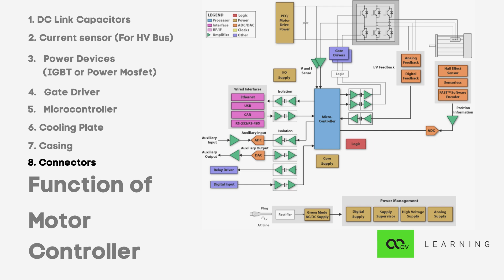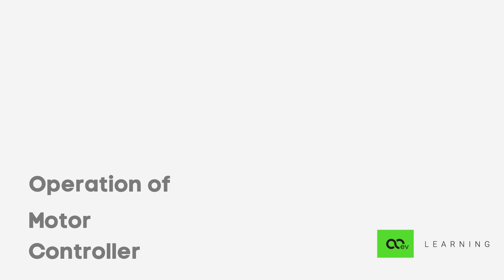Connection of higher voltages is solved by simple methods of lug-based connection with defined torques on the bolts to maintain the contact resistances in manageable levels. Specialized HV connectors are also used but they turn out to be expensive.